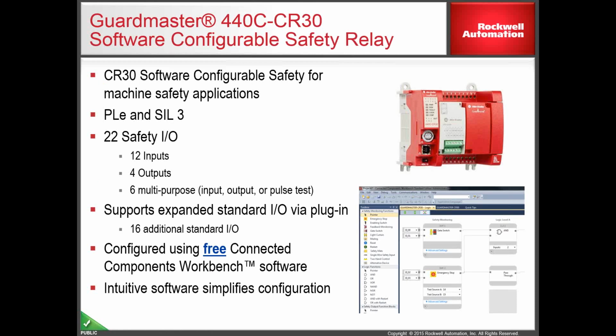Then we have the safety relay, which is CR30, which is essentially, as I said, used for smaller applications. It has 12 inputs, 4 outputs, and the IOs can be extended via plugin, which has 16 additional standard IOs. This can also be configured using Connected Components Workbench software.